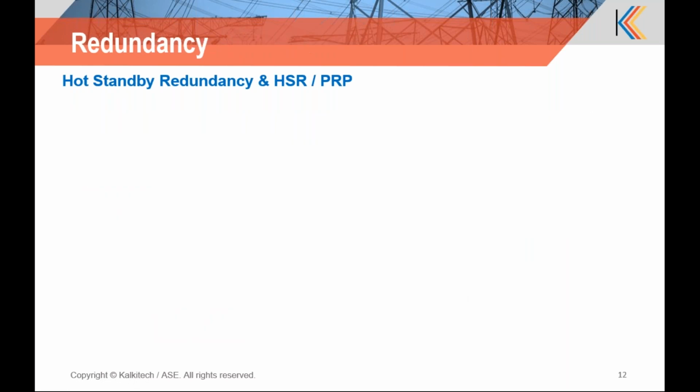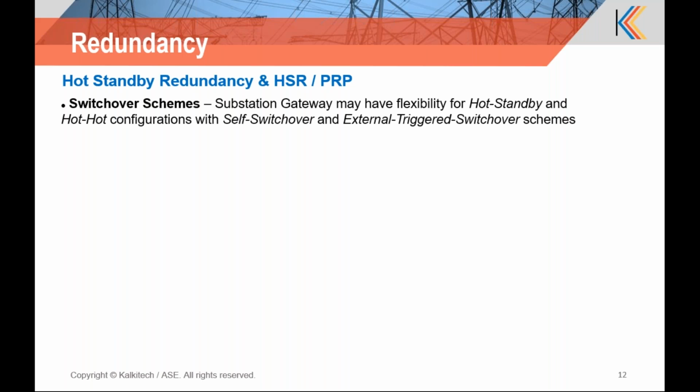Then redundancy, we support both hot standby, and it also has got hot-hot, and network redundancy mechanism. So switchover, we have a hot standby or hot configuration, and the switchover can be detected by itself. We call it a self switchover, or an external SCADA or a centralized system can issue an external command on the switchover point to trigger the switchover, and a mix of both self switchover and external triggered switchovers are supported.